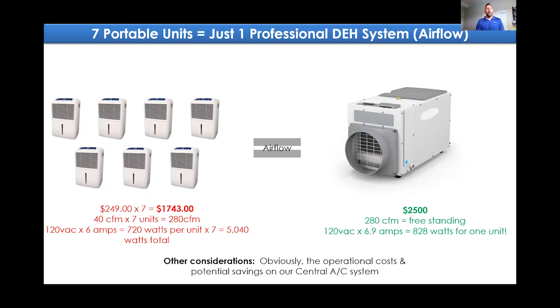Speaking more on airflow, if I took that 100 pint per day dehumidifier system, just to meet the same airflow requirements—just to move the same amount of air—I would need 7 of those portable dehumidifiers to equal the airflow. From a cost perspective, yes, I'd be about $800 ahead of the curve. But then consider the electrical consumption: each portable unit draws approximately 6 amps.